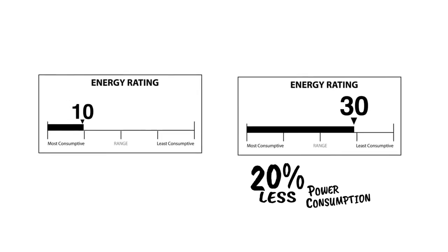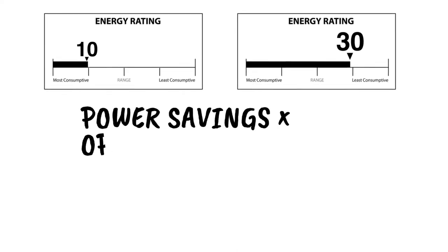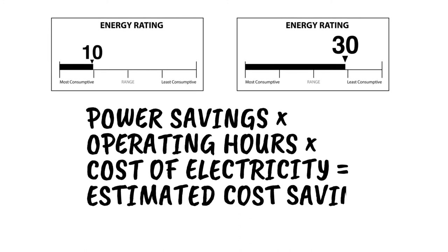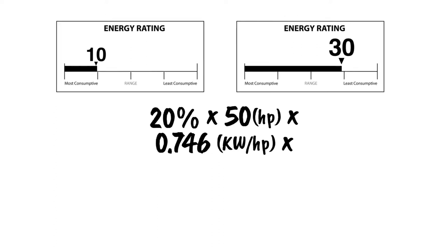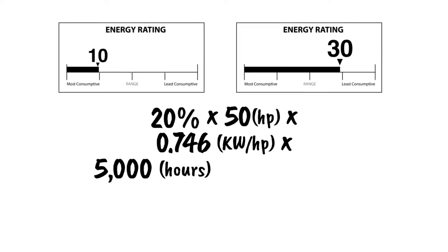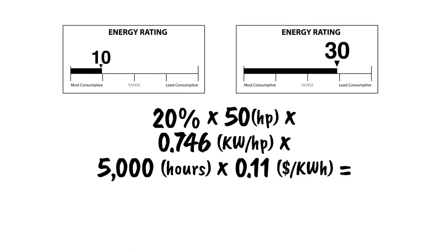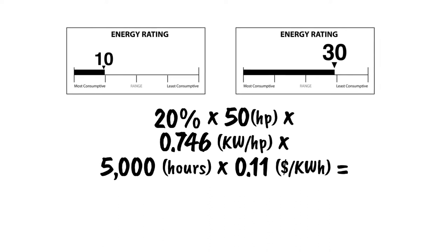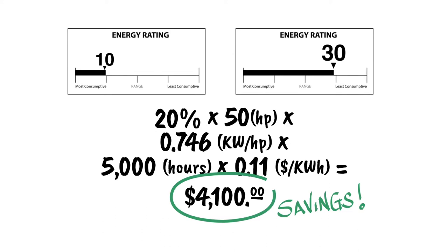Assuming DOE's average load profile, that equals 20% less power. Multiplying actual power savings by operating hours and cost of electricity yields the estimated cost savings. For example, in a typical 50-horsepower system operating 5,000 hours per year, using the average commercial energy rate in the United States of 11 cents per kilowatt-hour, a pump with an ER of 30 will have an estimated annual savings of up to $4,100 compared to a pump with an ER of 10.